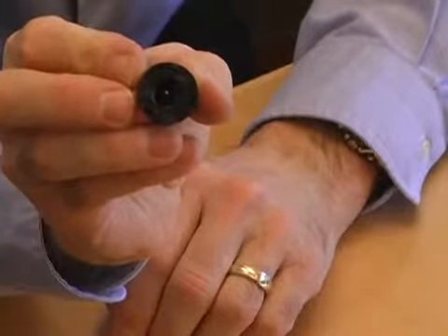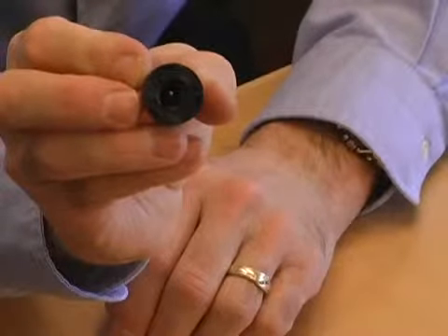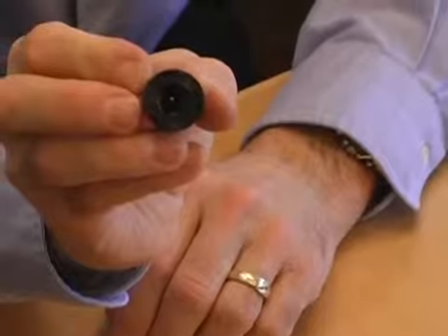Now being magnetic, it's a little bit newer technology. It's sealed, so it's very impervious to any sort of environmental conditions like dust or moisture or contamination. In this case, this would mount over the motor, and on the end of the shaft would be affixed the magnet. Now, this version is actually an absolute version, so this has information directly upon power up. So if you've got a piece of equipment anywhere that you need absolute position of an arm or a motor, you don't want to wait for it to start turning, an absolute encoder is the way to go.